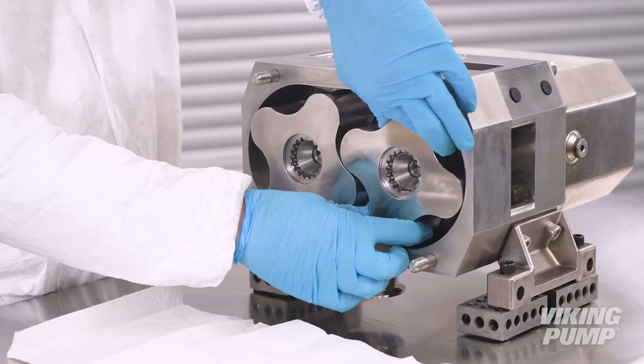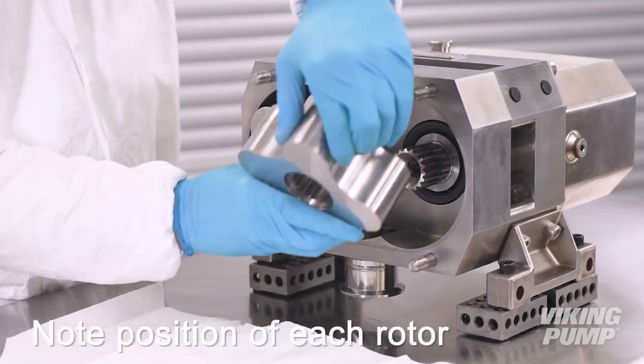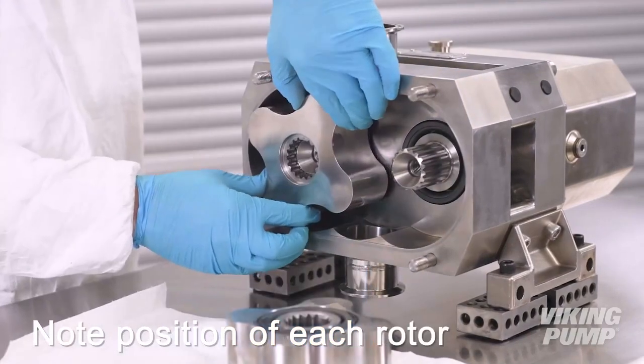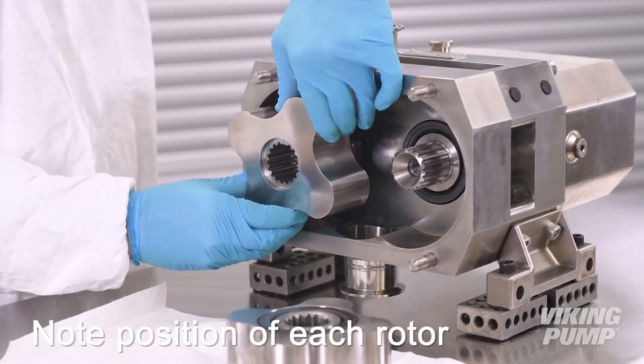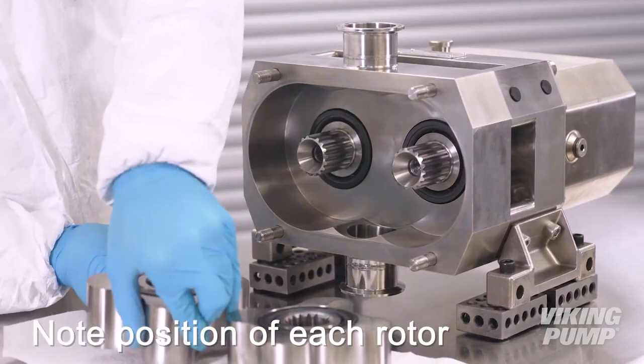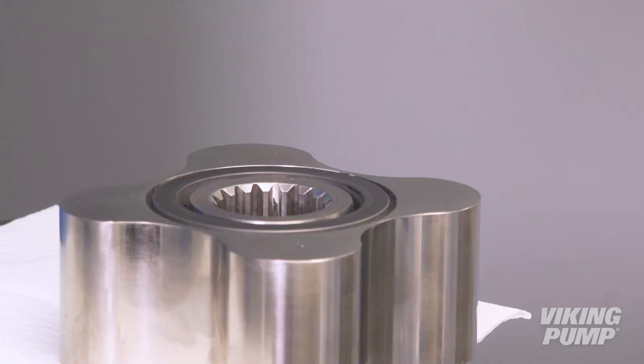Remove the rotors from each shaft. Note the position of each rotor, as they will need to be returned to the same position when reassembled. Next, remove the rotary seal face from each rotor. To do this, place the rotor face down on a piece of cloth or other non-marring work surface.